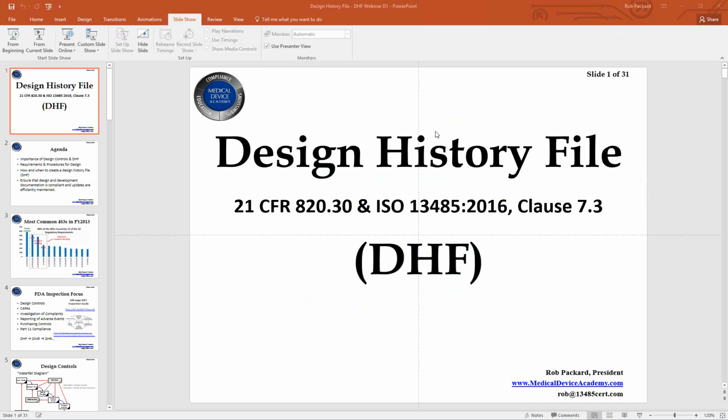That's pretty routine to do it that quickly for a high risk or a brand new product. If you have a product with very little change that's stable, that's been on the market for a long time, you might even be able to push it out to 3, 4, 5 years. So annual reviews might not be necessary, but you're going to review your post-market surveillance data on a periodic basis, and the annual is pretty common for a stable product that's been on the market and doesn't have a lot of adverse events.